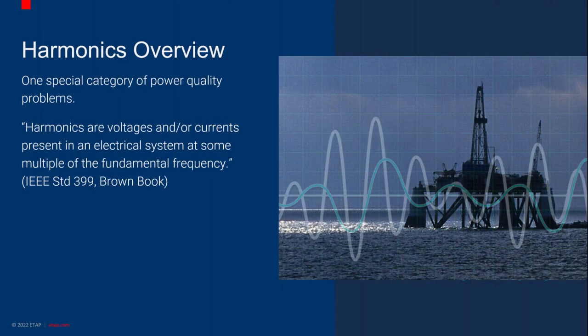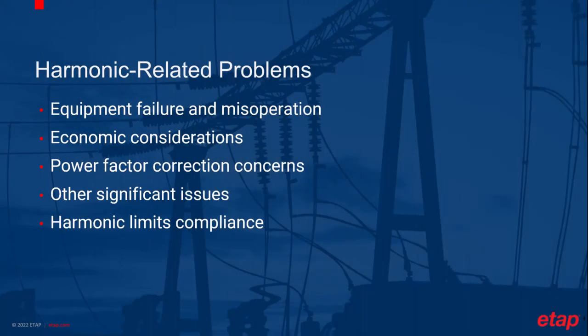Harmonics is one special category of power quality problems, which mainly deals with voltage and/or currents at some multiples of the fundamental frequency caused by nonlinear load on a power system. Many problems can be caused by harmonics, such as equipment failure and misoperation. The symptoms include the overheating of motors, cables, transformers, neutral wires, motor vibrations, nuisance circuit breaker operation, generator regulator malfunctioning, and so on.